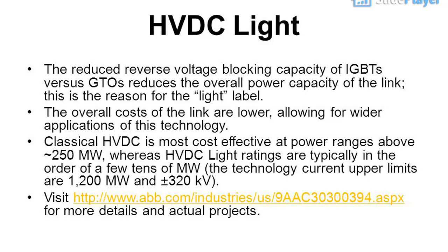HVDC Light: the reduced reverse voltage blocking capacity of IGBTs versus GTOs reduces the overall power capacity of the link — this is the reason for the 'light' label. The overall costs of the link are lower, allowing for wider applications. Classical HVDC is most cost effective at power ranges above ~250 MW, whereas HVDC Light ratings are typically in the order of a few tens of MW; the technology's current upper limits are 1200 MW and ±320 kV.